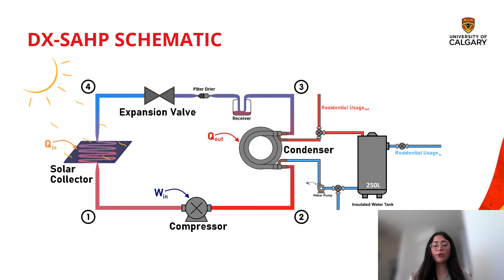Following compression by the compressor, the refrigerant flows into the coaxial condensing coil, and this is really where the magic happens. Within the condensing coil, the refrigerant, at a higher temperature than the pumped domestic water, rejects its heat to it, rendering it ready for domestic use. To continue the cycle, the now cooled refrigerant is depressurized via an electronic expansion valve and flows back to the solar thermal collector, where it experiences more useful heat gain and repeats the cycle.